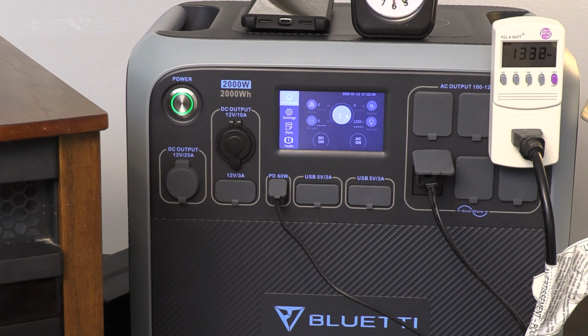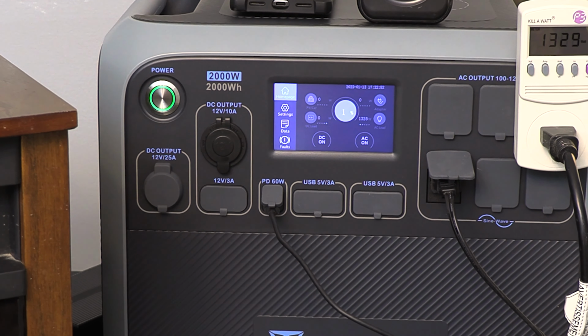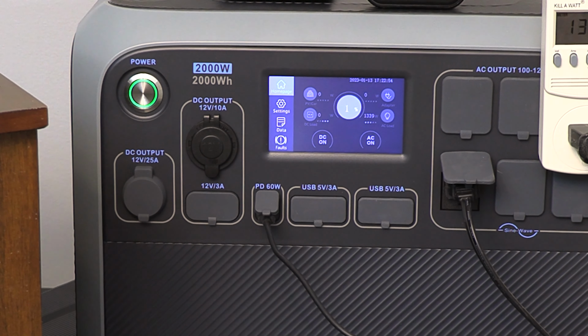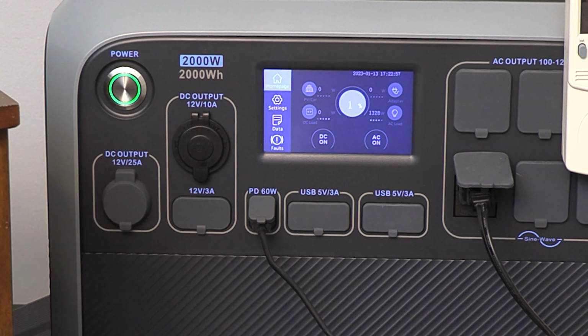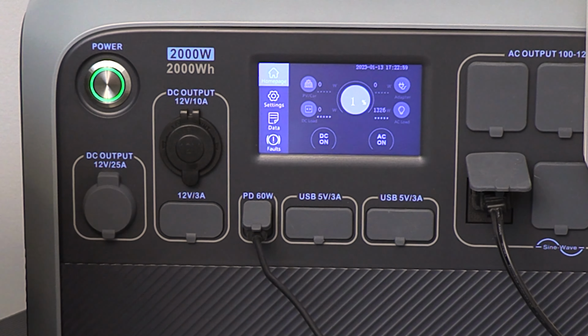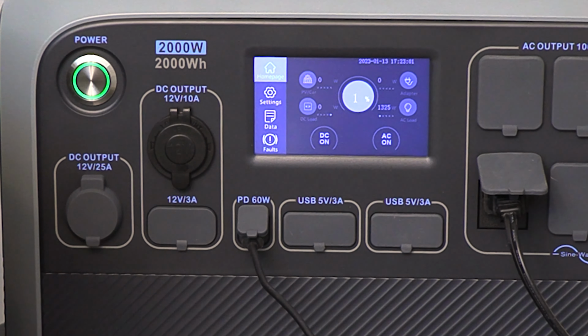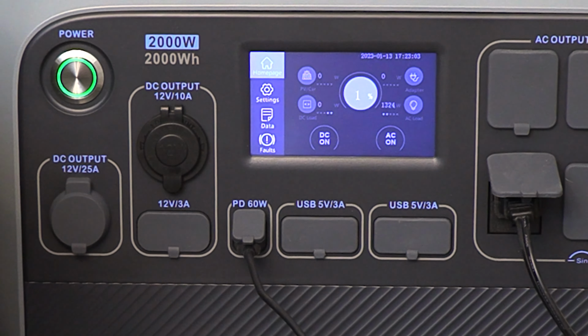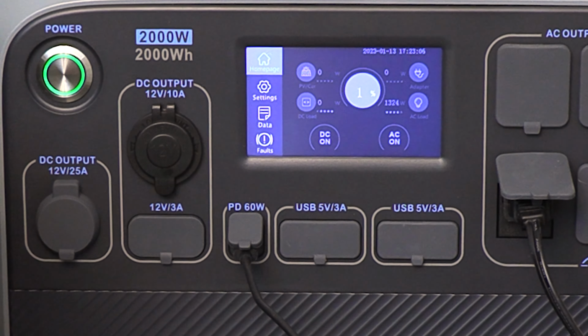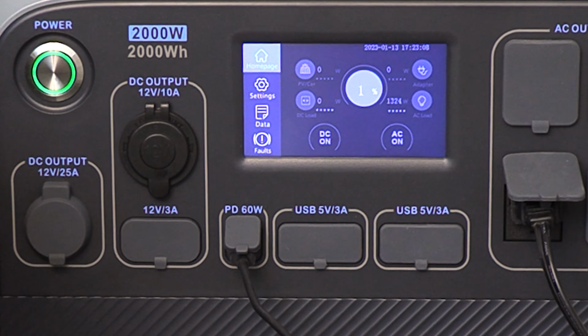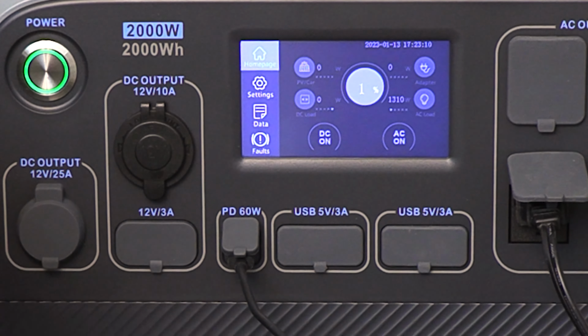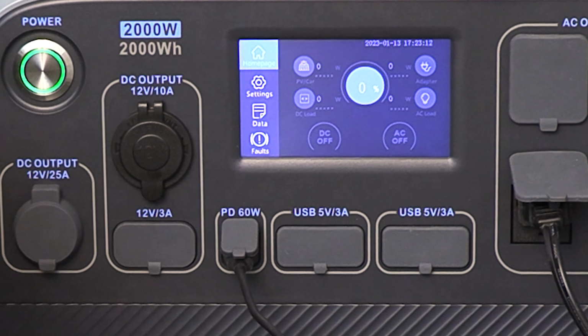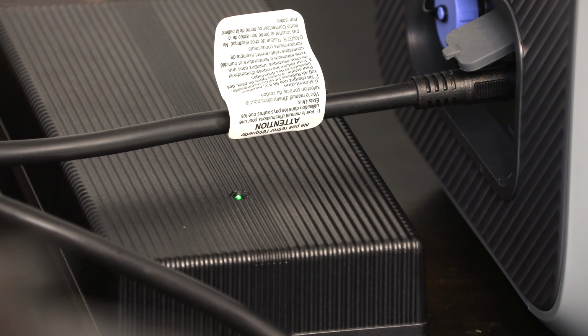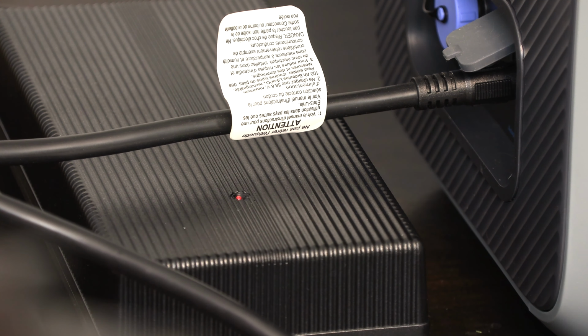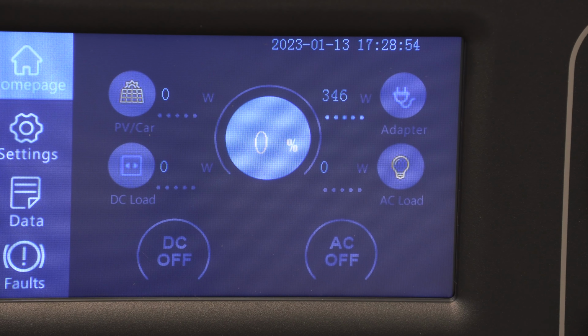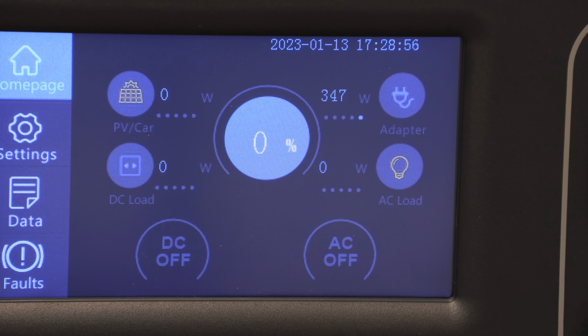Some of the bigger units and other brands will have a battery warmer in the bottom of the battery to allow it to stay warm even when it's really cold outside. Again, lithium iron phosphate batteries have to be above 32 degrees Fahrenheit to take a charge effectively. Anything below 32 degrees can actually damage the chemistry of the battery. Keep in mind that feature will cost a little extra money, and it probably won't come into play in most of the lower 48 states.